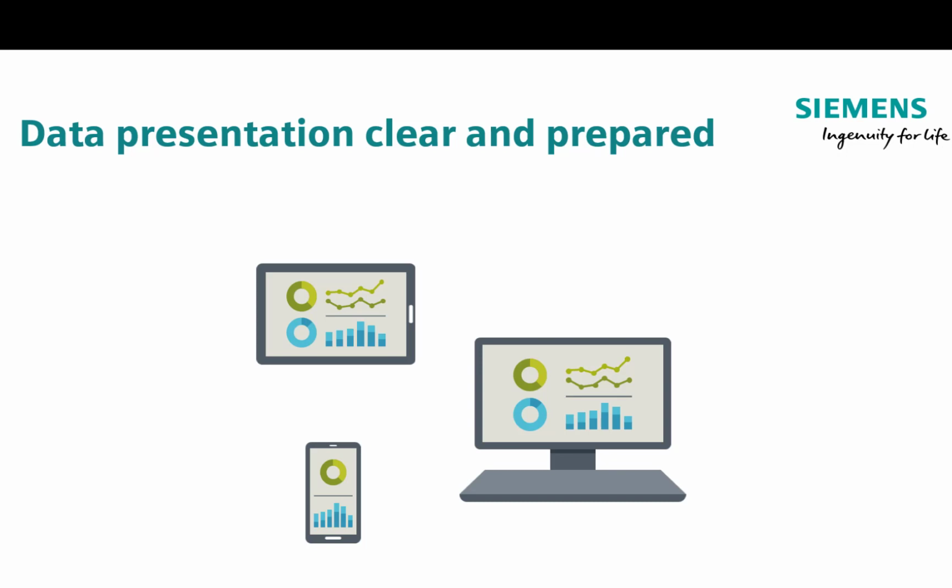Of course, we're going to get the odd occasion where you change the process and the instrument fails. And we haven't logged, that's not been a gradual occurrence, but the beauty is if you've been logging the data, you'll see all of the intelligent data before and after you made those process changes. So it might be that you've decided to increase the speed on an agitator to mix the product quicker, but because you've done that, you've created an issue with foam. Well, the diagnostics from the radar device at the top of the vessel will give you an indication of what's happening with regards to the measurements and the possible causes.